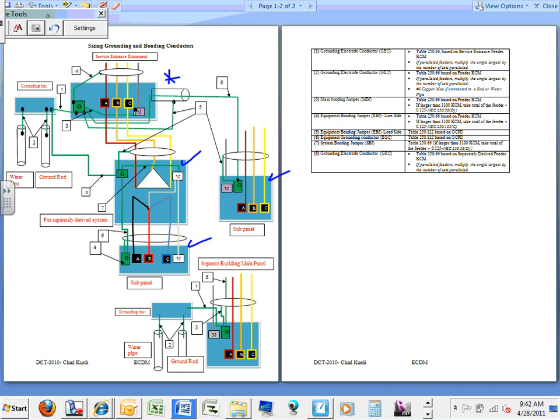So what are you guys supposed to do? We're supposed to size everything green. Everything green is bonding and grounding. Everything colored, obviously, is not. So I'm going to draw a couple of things, guys, to give you an idea. Most likely this will be a 480/277 volt system. This transformer will be 480 on the primary. On the secondary will be 208/120 volt.